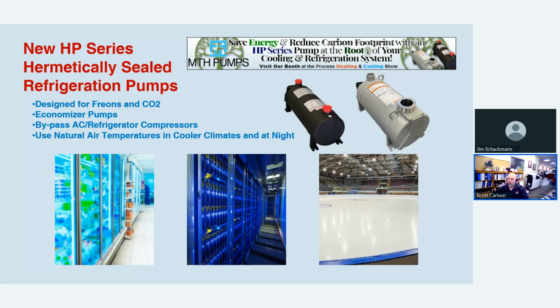One of our newer applications we started getting into is our HP series. This is our very first welded, hermetically sealed pump. The entire pump is built inside, and then it's welded shut so that there is absolutely 0% chance of leakage. It's designed for running freons, refrigerants, and CO2. It can handle a case working pressure of, I think, 800 psi. More. They use them for economizer packages as well as two-phase cooling and direct-to-chip cooling in data centers and computer processes.